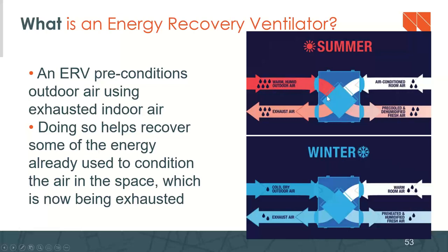In most residential ERVs or HRVs, this core is what we call a flat plate core. In larger buildings, there might be a wheel, something that actually spins to get the heat recovery to happen. There are some residential ventilators that use a wheel as well, but the majority are flat plate. And so doing this preconditioning, this energy recovery, helps recover some of the energy already used to condition the air in the space, which is now being exhausted, right? So it's swapping this. These airstreams don't actually mix, but the energy of the airstream is what is transferred.